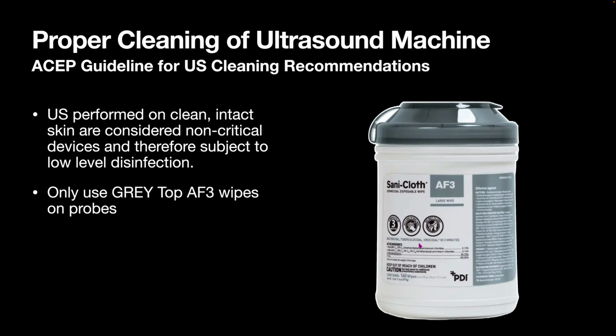But for our purposes, when you're at the bedside, you're performing an ultrasound on intact skin. After you're done, you clean it with the gray AF3 wipe. And you only use the gray AF3 wipe. I mean that, because if you use the purple or the orange, over time that's going to degrade the probe, and the probe is extremely expensive. Only gray AF3 wipes on the ultrasound probe. I would recommend them on the machine as well. The orange bleach wipes leave a film.